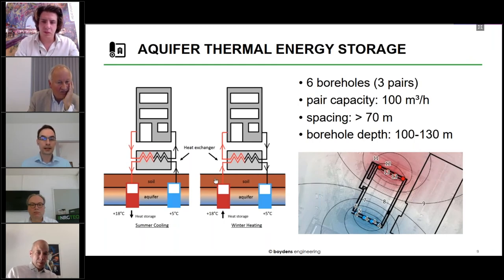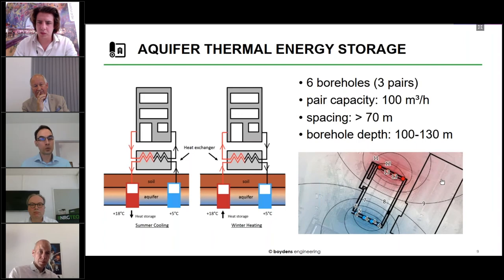So what is happening here, in fact, is that in summer, when there is more cooling necessary, we produce more hot water, and that hot water is injected on the side of the warm boreholes. Whereas in the winter, when we have to heat and there is more cold water that is produced, the cold water is injected in the cold sources. And of course, in the meantime, so in spring and in autumn, the systems can be switched over from one to the other depending on the needs of the building.